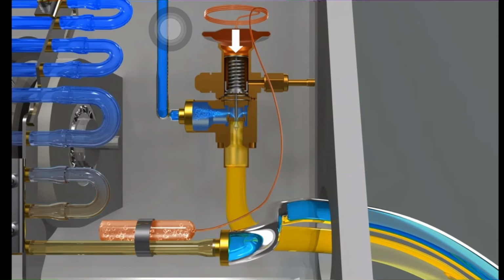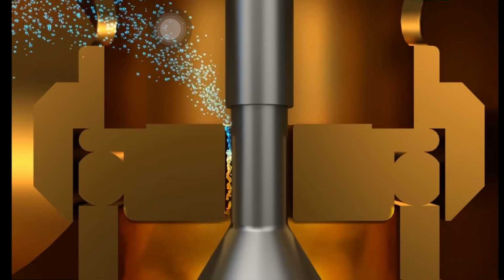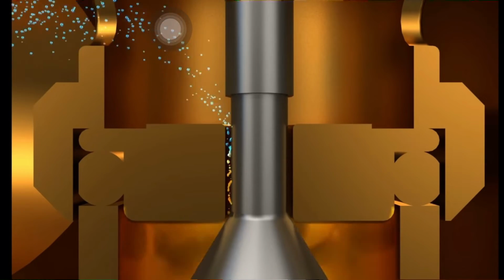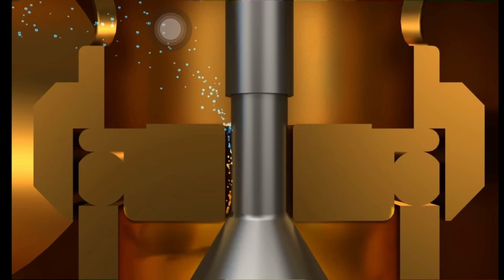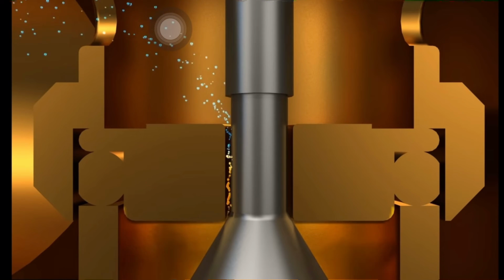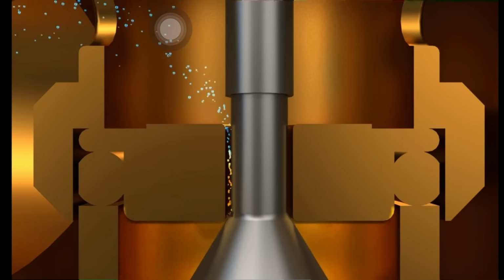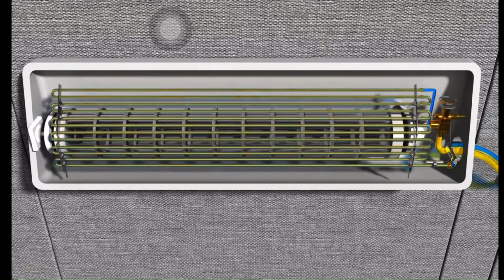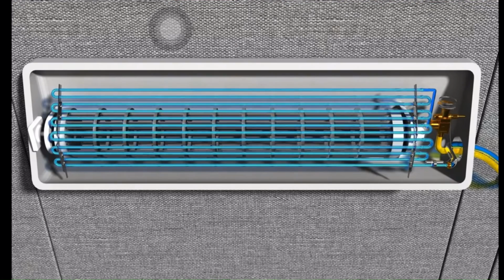When the temperature at the exit of an evaporator drops, gas pressure drops and the amount of refrigerant going into the evaporator in turn drops too. Applying the above principle, an air conditioner controls the amount of refrigerant injected into an evaporator to prevent overcooling. A refrigerant passes through the pipes of an evaporator and takes away heat in this process. As the fan underneath starts to operate, warm air in the room is sent to an evaporator and cooled air is emitted.